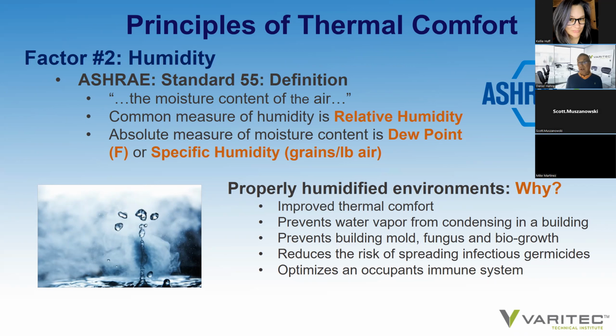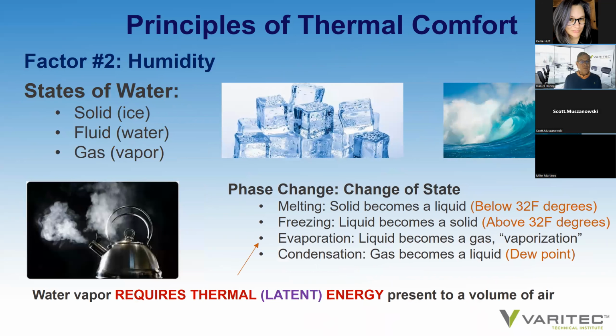It's to prevent water vapor from condensing in a building at diffusers or in windows. Prevents building mold, fungus, and biogrowth. Not a good thing to have. Reduces the risk of spreading infectious germicides. Studies came through in the pandemic that a properly humidified building at between 40 to 60% RH is better conducive to human health and the efficiency of operation of our immune systems, as well as reduces the risk of infection, because dry environments result in aerosolized, desiccated pathogens becoming airborne, and consequently the environment becomes more infectious. So very interesting studies have come forward through the pandemic that reference humidity as an important factor to be considered to reduce the risk of infection.